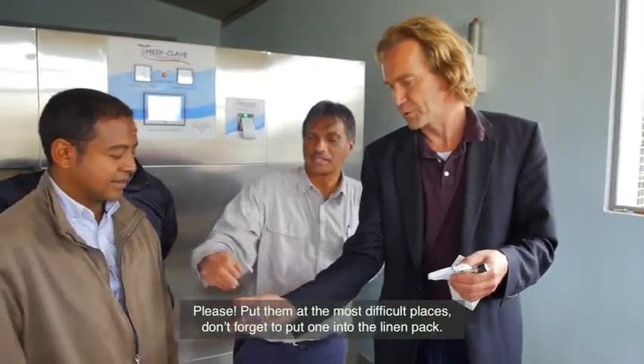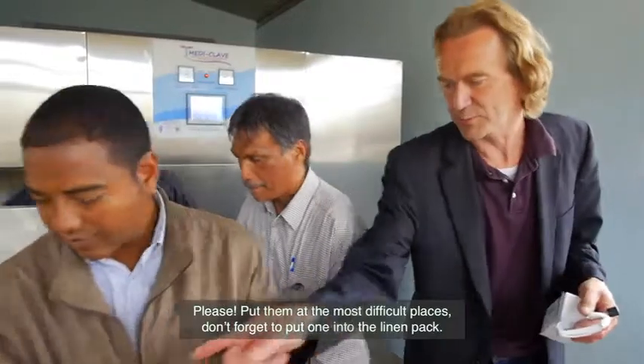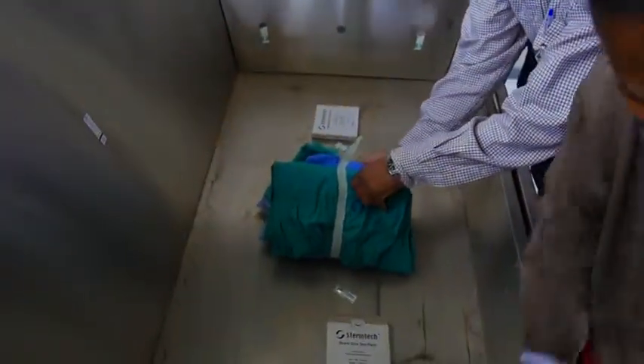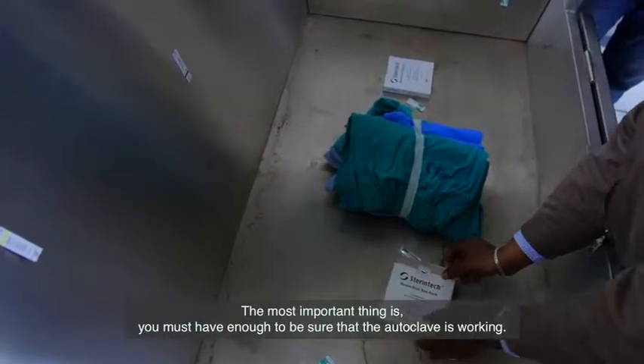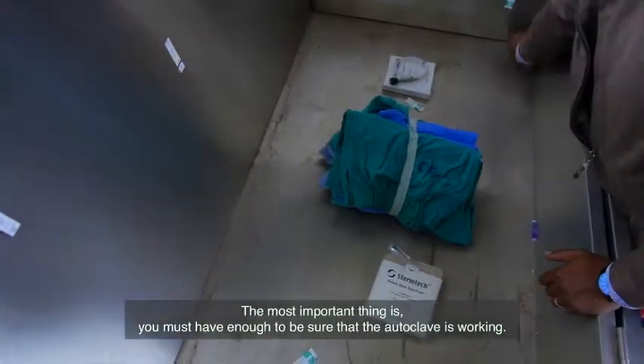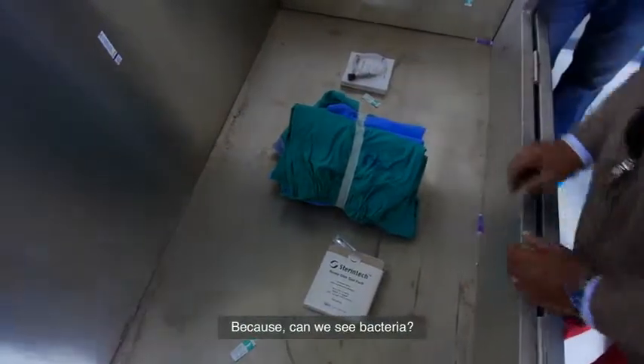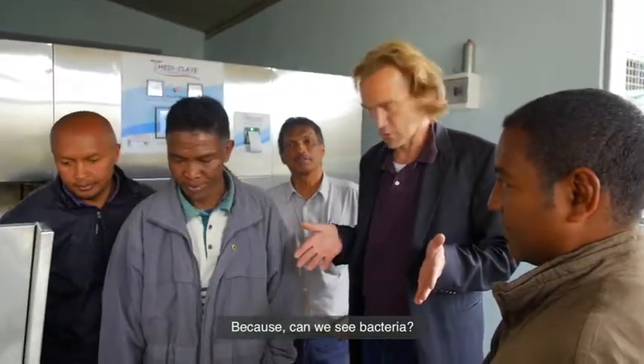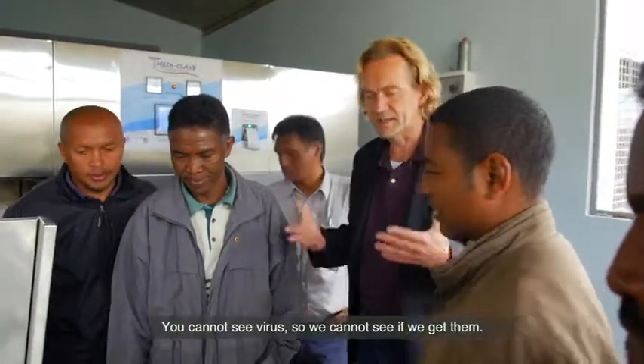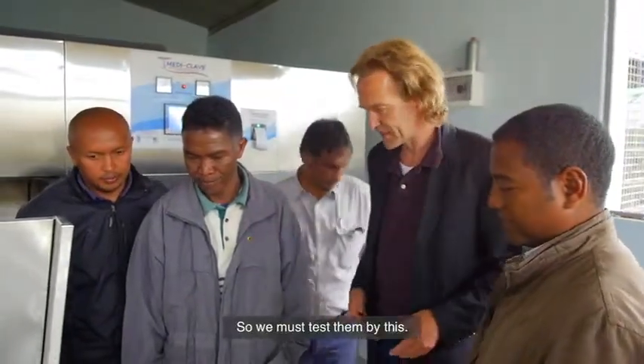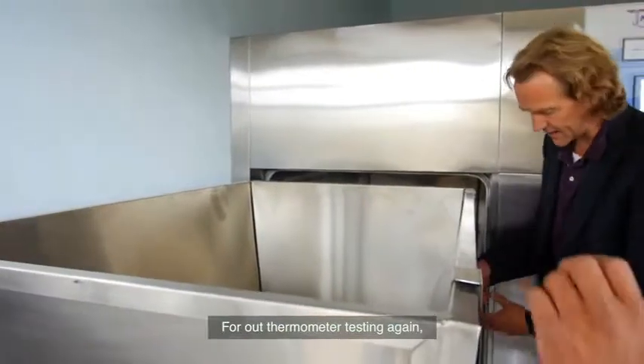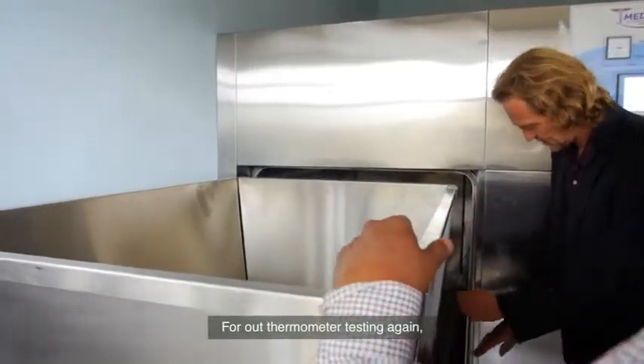Please. Yeah, put them at the most difficult places and don't forget to put one into the linen pack. Most important thing is you must be 100% sure that the autoclave is working. Because can we see bacteria? No, we can't. We cannot see virus, so we cannot see if we killed them. So we must test it by this. Going for thermometry testing again. We keep one outside.